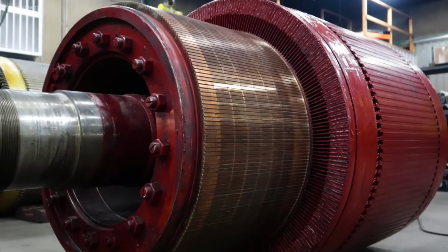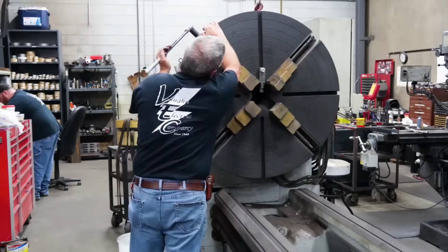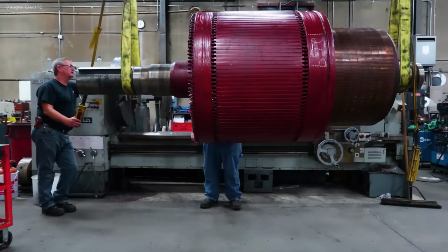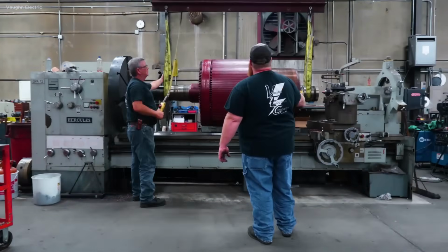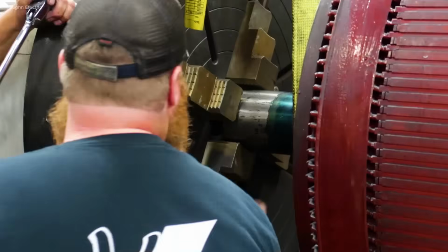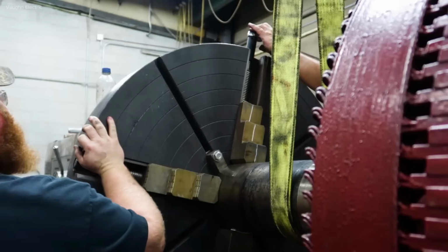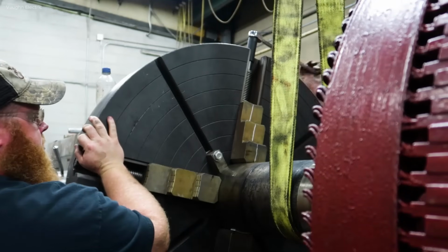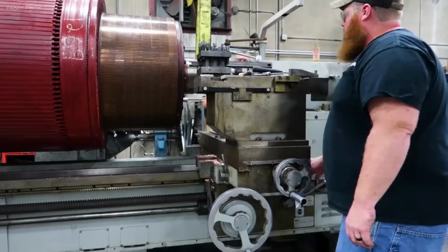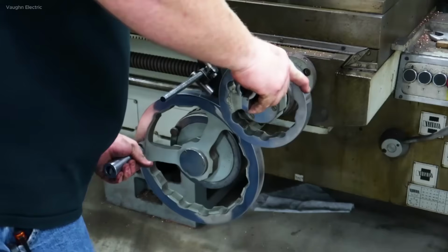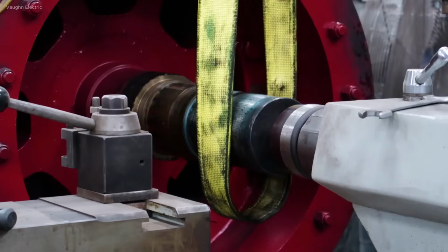After cleaning, visual inspections are performed to detect cracks, hot spots, or mechanical damage. The stator windings are tested with a high potential test, and insulation resistance is measured with a Megger tester. If the windings fail, the stator is rewound. The old copper wire is removed, and new coils are wound according to the original design.